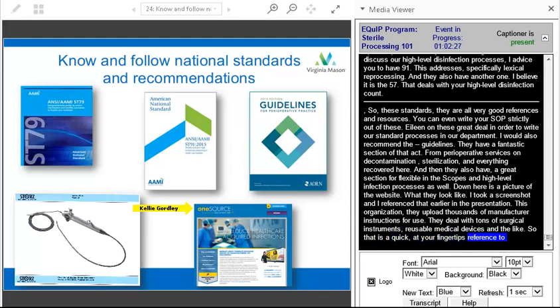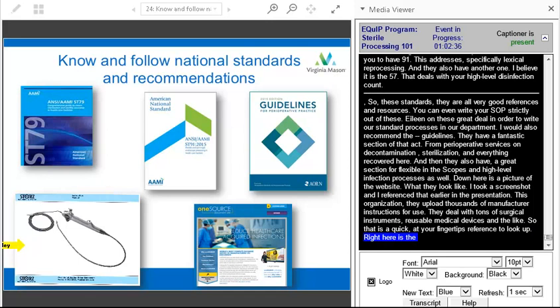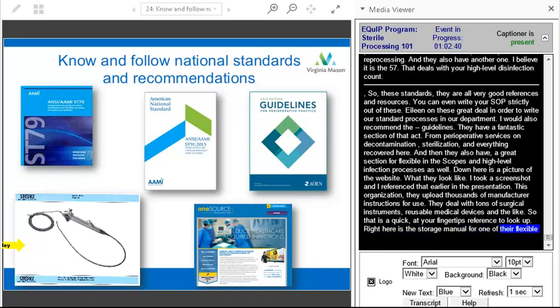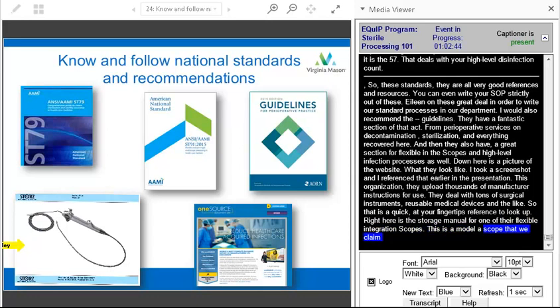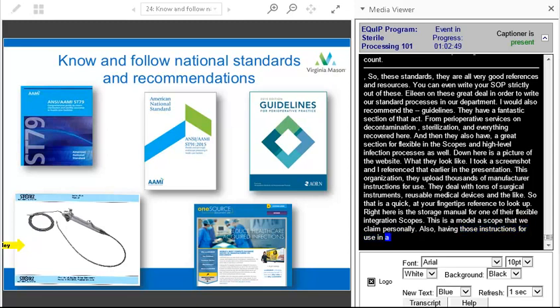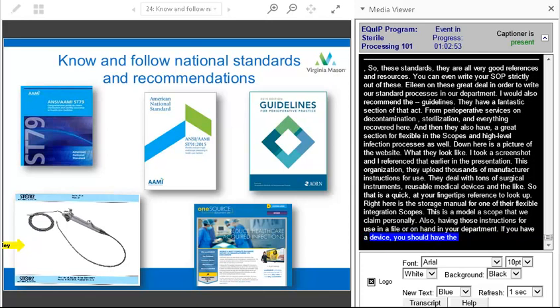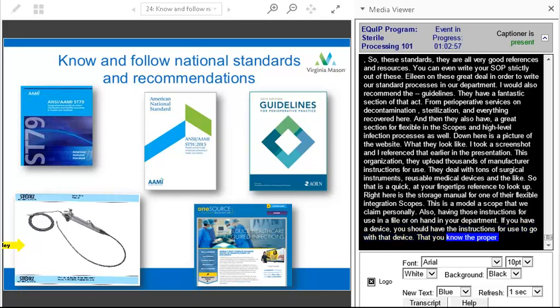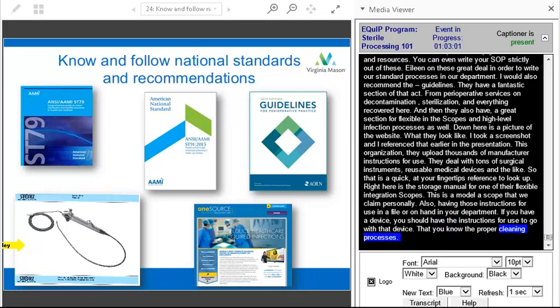And then right here is a manual for one of their flexible intubation scopes. This is a model of scope that we clean personally. So also have those instructions for use in a file or on hand in your department. If you have the device, you should have the instructions for use to go with that device, so that you know the proper cleaning processes, inspection processes, as well as any sterilization processes that go with that device.